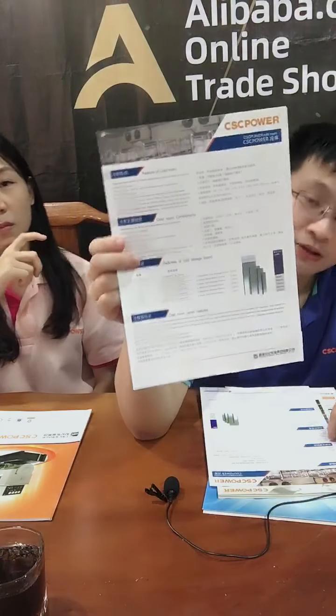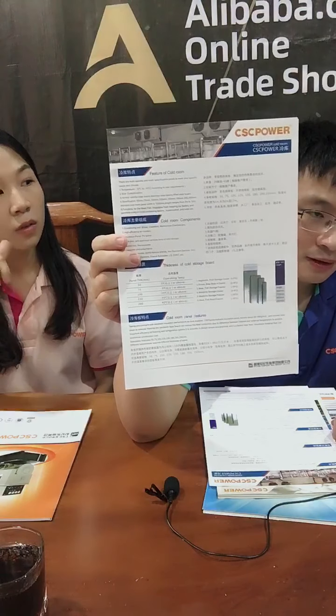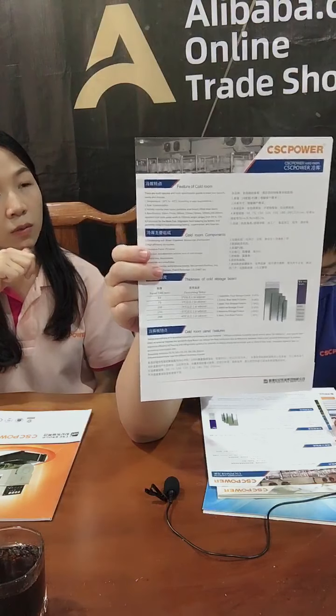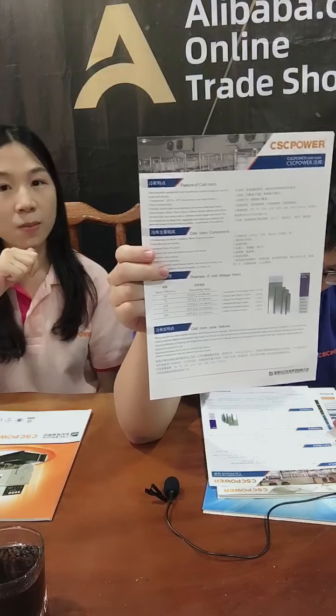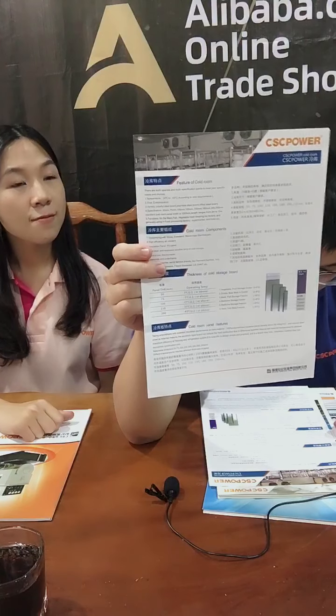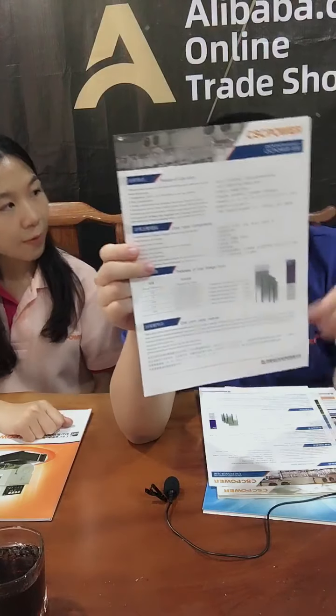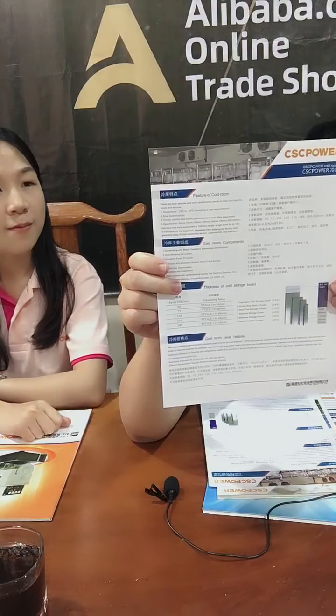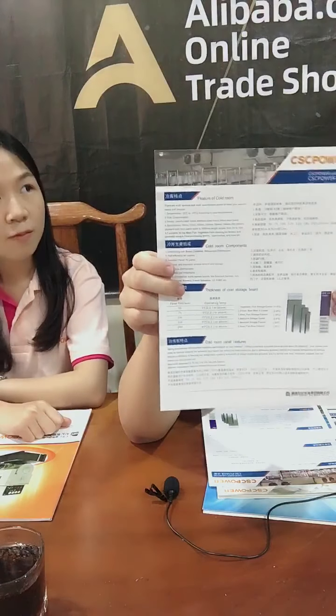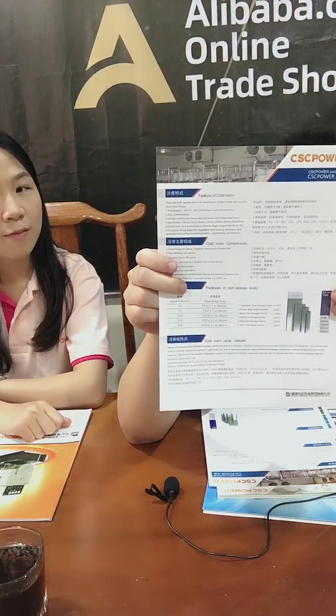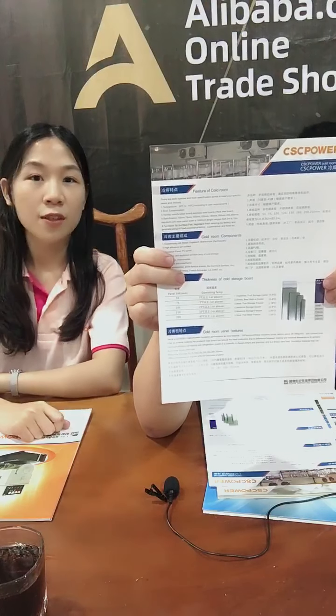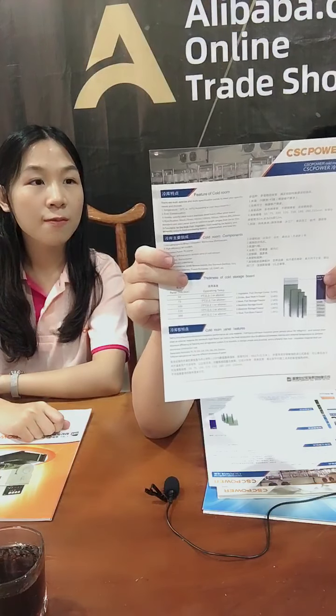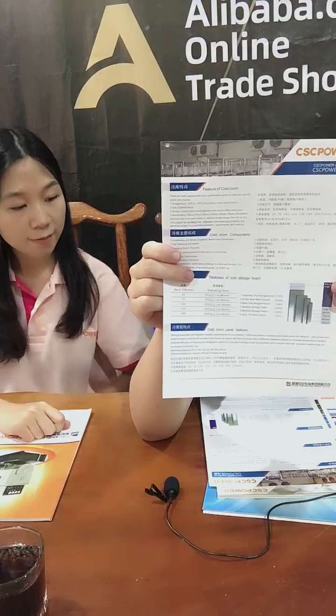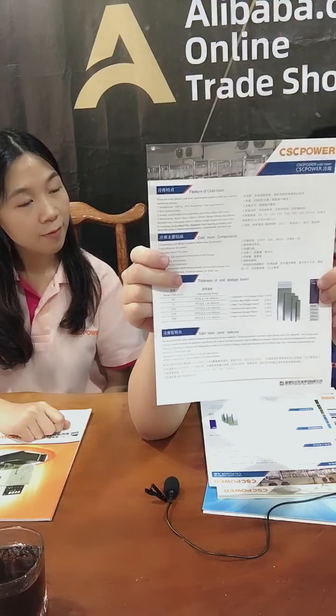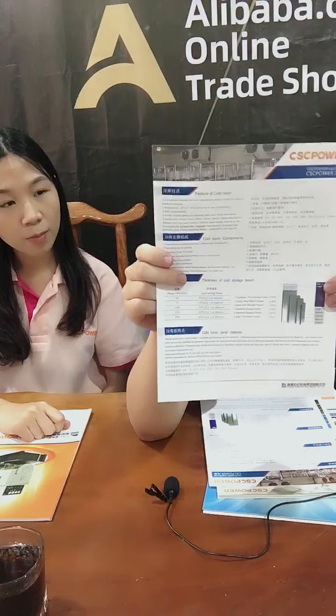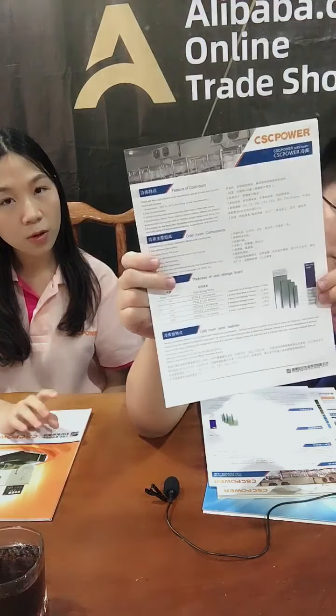For fruit storage at about 4 degrees, you can use 50 millimeter panel if your environment is very cold. Normally you can choose 75 millimeter panel for 4 degree cold rooms. If you are in Africa or the Middle East with hot air, you can try 100 millimeters for better insulation.